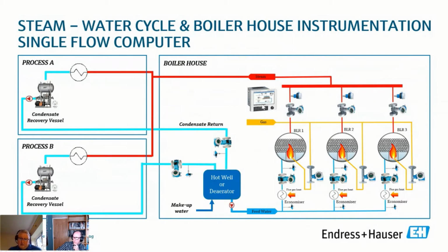No, these data managers can take legacy equipment, so anything that's already measured. If there was a mechanical turbine meter on the gas, then that just needs pressure and temperature. We could pull those in and do a corrected volume calculation here, so now we've got the right units. We can get the energy measurements. Similarly, if we haven't got the heat, we can do the heat calculation in here as well. That's a powerful piece of kit.